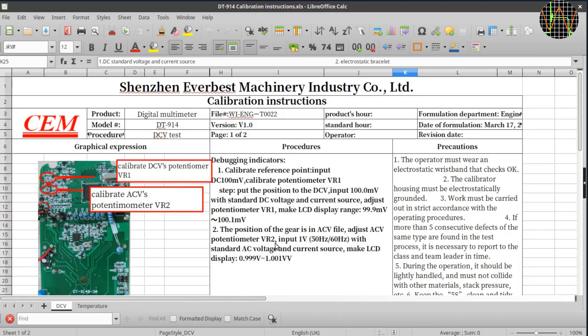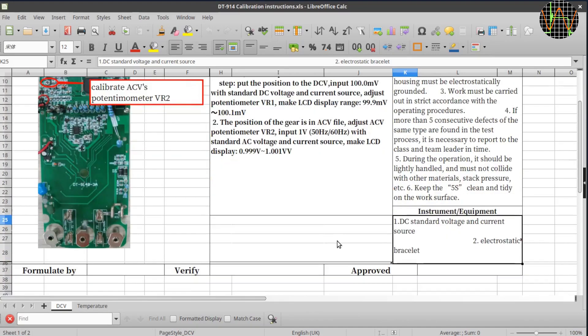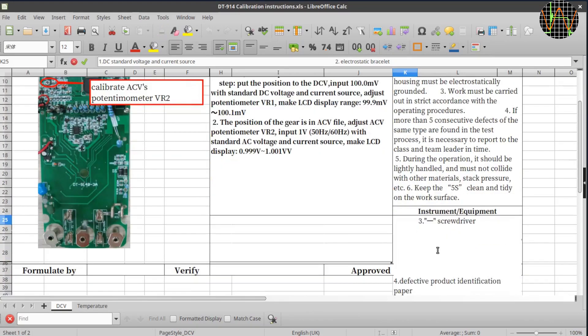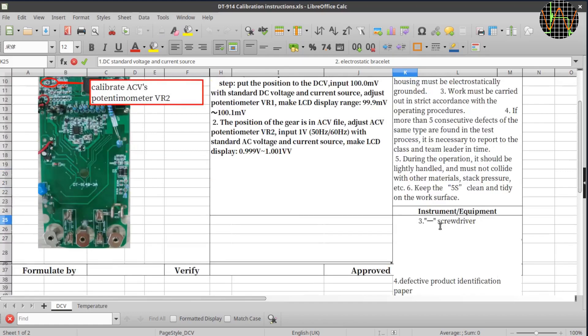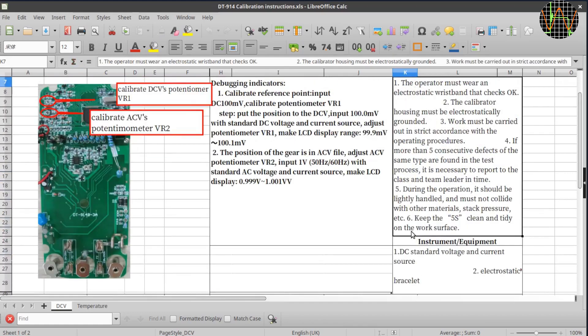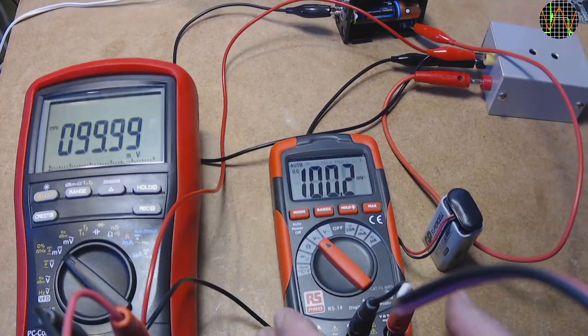The calibration procedure called debugging indicators for some reason is simple enough. Put the meter into the 100mV range, apply 100mV and adjust VR1 until it reads 99.9 100 or 100.1. For AC, the procedure is similar but to be performed with 1V AC, 50 or 60Hz and adjusted with VR2. No word on the shape of the waveform but being an averaging meter it has to be sine wave of course. Sadly, it does not specify the type of equipment or calibrators used and the only other information is that a static wristband must be worn and the calibrator must be grounded. Interesting that if the operator finds 5 consecutive defects of the same type, they need to report it. I guess that would mean a flaw in the assembly process.